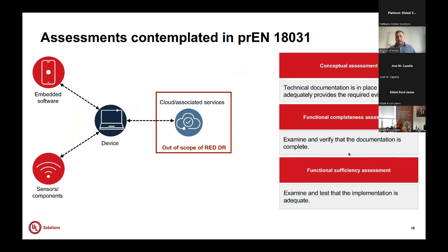The scope of the standard is only of the device itself and the components that are in the device. Whatever is outside the device, cloud associated services, is not under the scope of the regulation itself. But of course, manufacturers are responsible for what is happening anyway for their devices. Not that they need to close their eyes because it's outside the scope of that, because the manufacturer remains still responsible for the ecosystem that is around the device. So I want just to clarify that point, because it's also explained in the Blue Guide 2022.